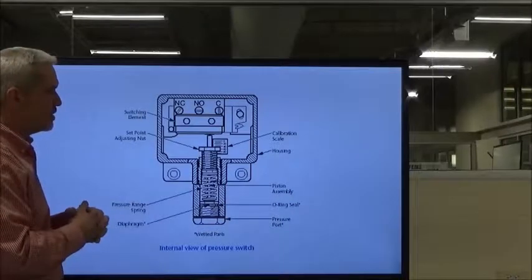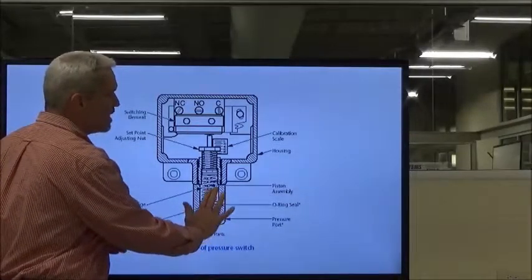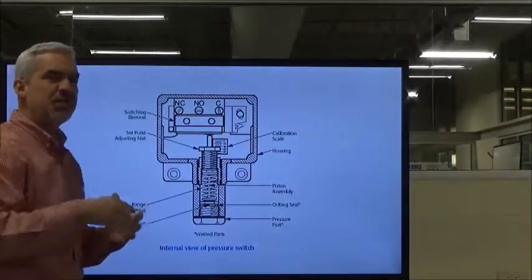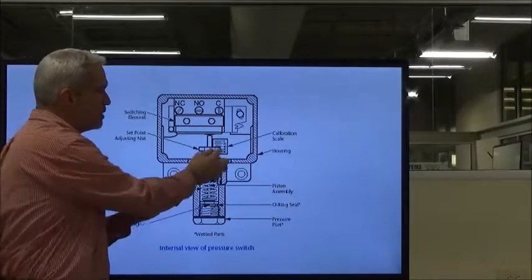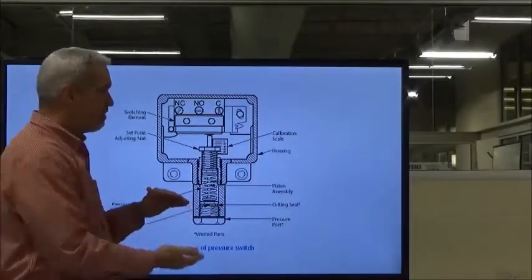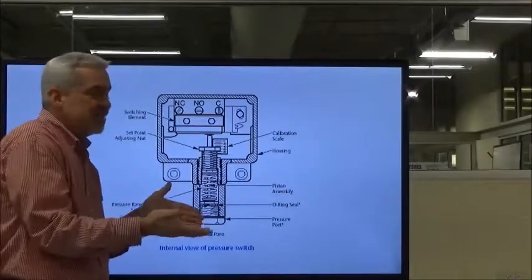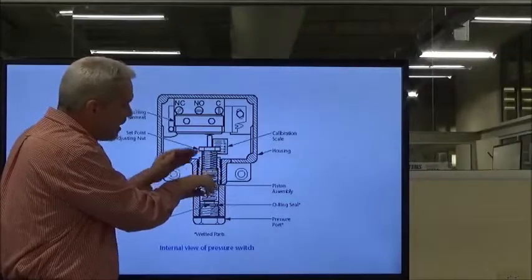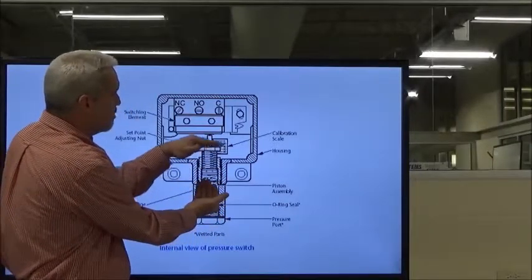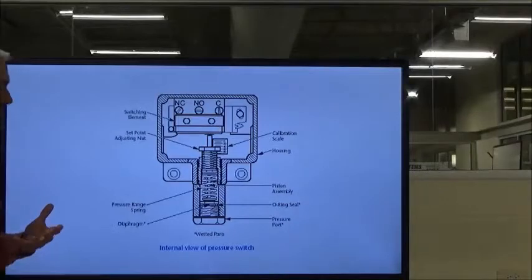The way this works is when we tighten this adjustment down here, we're applying more and more spring pressure. The more spring pressure that we have, the more fluid pressure it's going to take to actuate that piston and get it to make these contacts open or close. So, if we want to set our switch to, say, 50 psi, it takes 50 psi of fluid pressure to offset that spring so that the piston can raise up and the actuator can touch the switch and make it change. If we want it to actuate at 75 psi, we'll dial our knob, run it down and compress that spring.